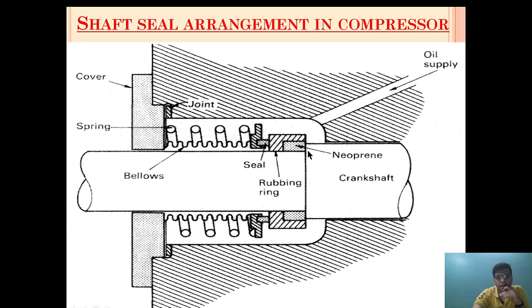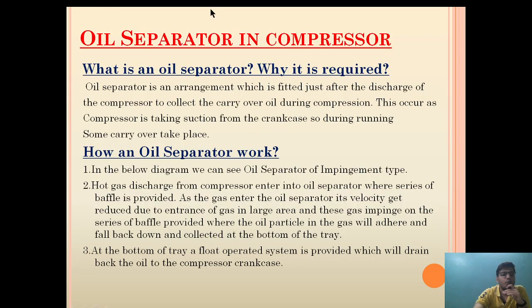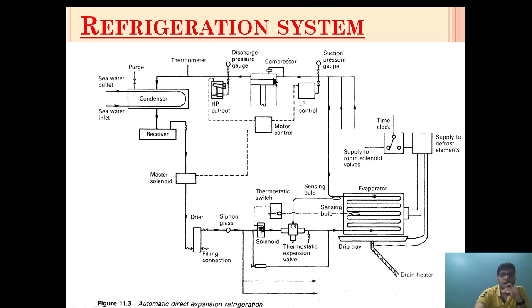The parallel and perpendicular leakage is arrested as described. Now, why is an oil separator used in a compressor? An oil separator is an arrangement fitted just after the discharge of the compressor to collect carry-over oil during compression. This occurs because the compressor takes suction from the crankcase, so during running some oil carry-over takes place. After the discharge, an oil separator arrangement is provided.